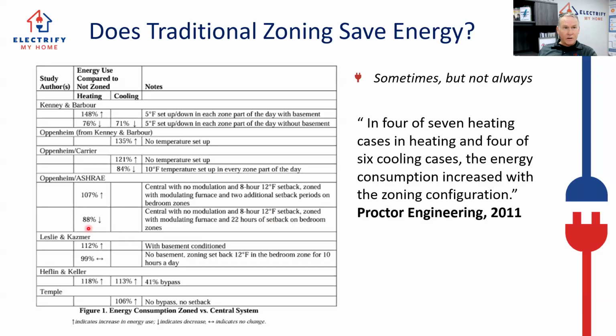A good rule of thumb is if we are going to be heating and cooling an area that hasn't been heated and cooled effectively before, it's going to use more energy to do that, because we're taking care of a load that we weren't dealing with before. So if the unit is now just going to run upstairs to take care of the cooling upstairs, they used to be hot, now they're cool, the bills are going to go up.